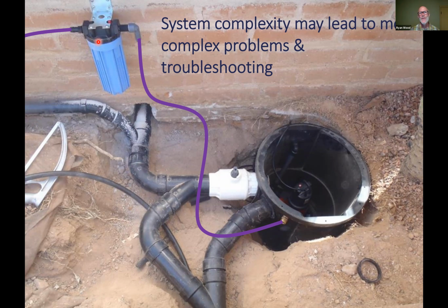So if your gray water sources are all below grade, so too low in the ground to be able to get that water up and out above ground, then collection distributions start to make sense. But keep in mind that filter has to be in place, because if you take that filter off, then your whole irrigation line is going to fill up with gray water. It's going to clog up with gray water particles. Or say, okay, I don't take it off, but I get lazy and I don't clean it. You're going to burn up the pump. Okay. So if you don't clean the filters, then your pump could burn out.